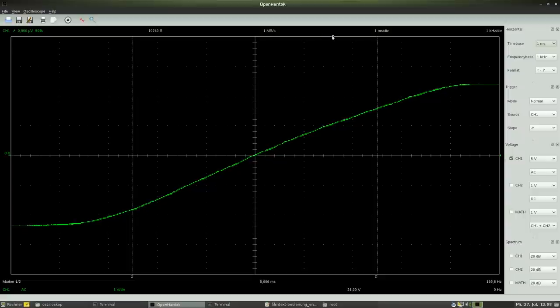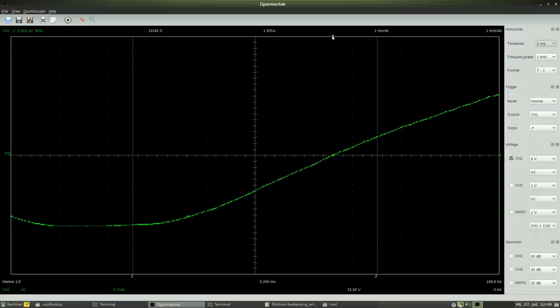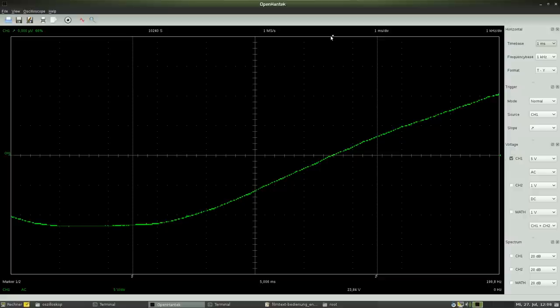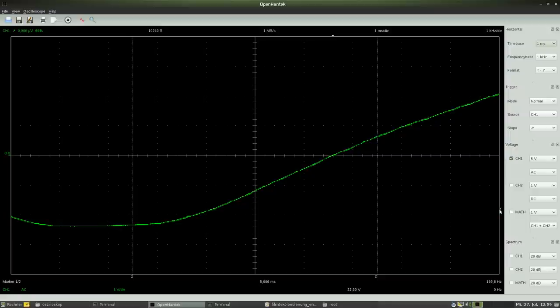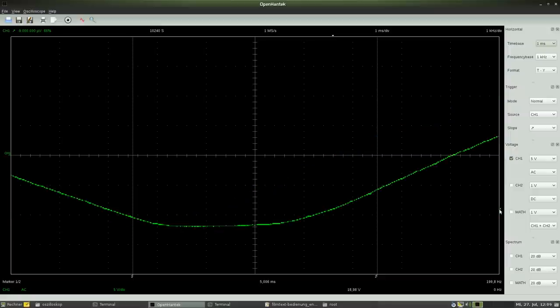Let's move the point of triggering some more to the right, so we can observe a larger area of the curve to the left of that point. With the help of the trigger level and the point of triggering, we can observe different areas of the curve progression.